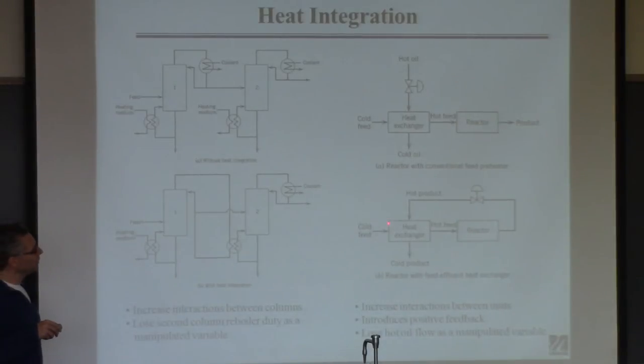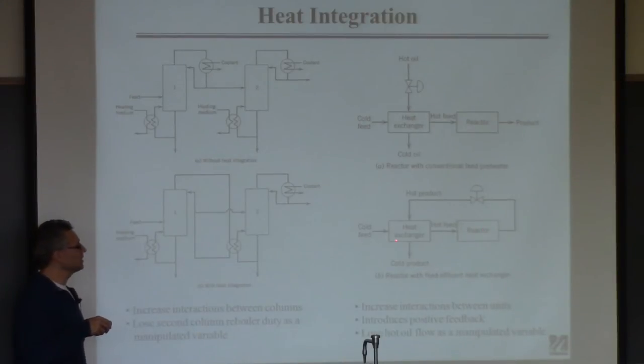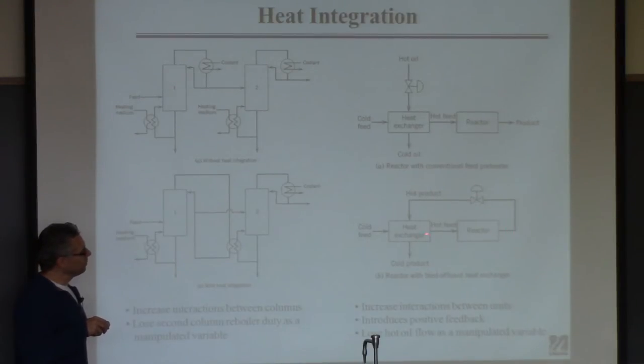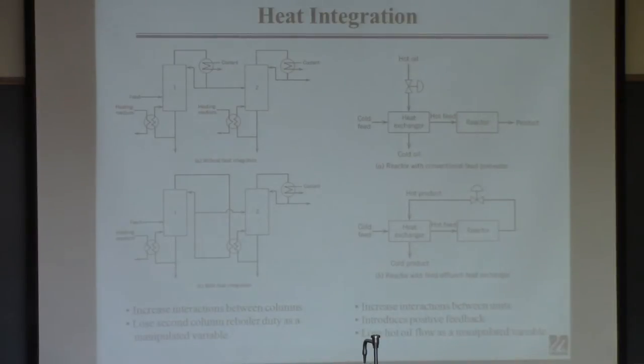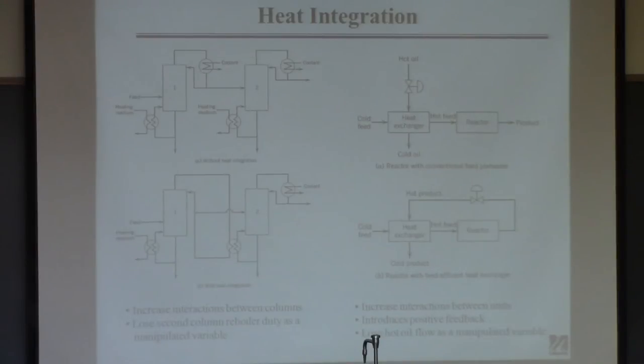But it does create a problem: the exchanger affects the reactor, which is what we want, but now the reactor also affects the exchanger. You can imagine something bad: you heat up the reactor effluent, it gets hotter, more reaction occurs, it gets even hotter — and this might actually go unstable. Unstable in a plant doesn't mean a line goes to infinity; it means the plant explodes or catches fire.